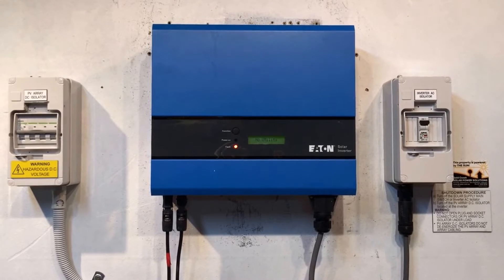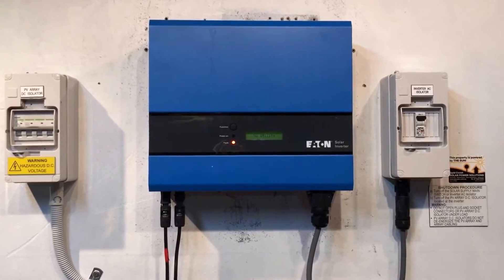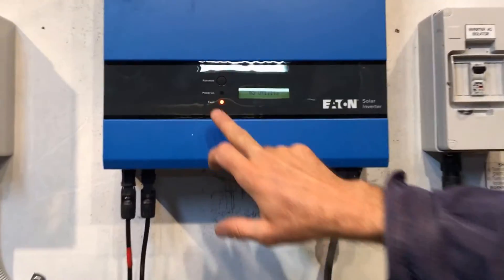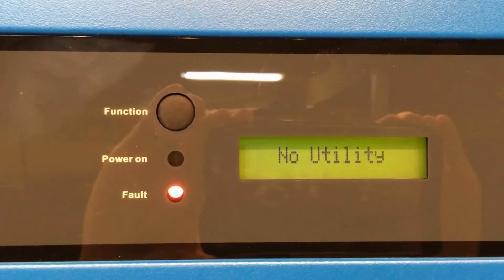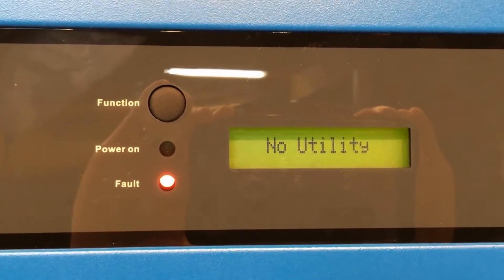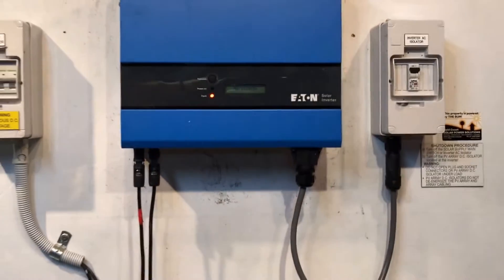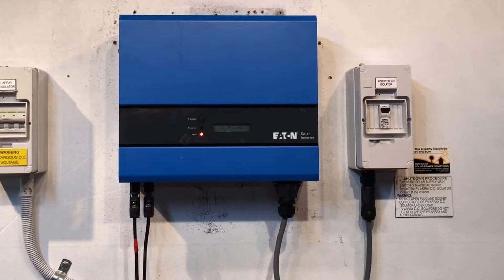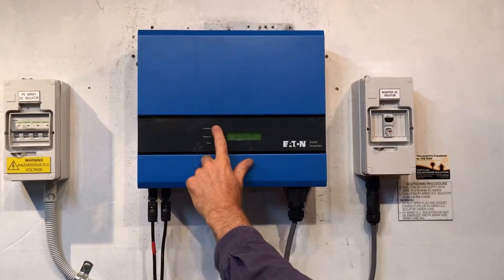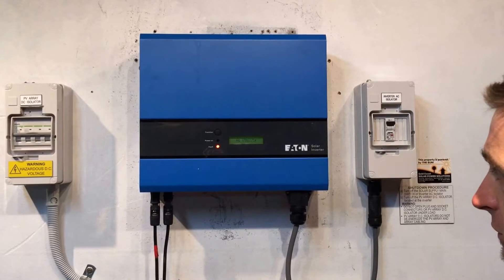Hi, Simon here from Goldco Solar Power Solutions. Today we have an Eaton solar inverter and you can see on the screen it's coming up with 'no utility' and the red fault light is on. If you ever see the red fault light on, that means the system is not working — you've got a problem that you want to rectify pretty quickly to get your solar power system back in action. When it has a fault light on, it tells us what's going on on the screen: it says 'no utility'.